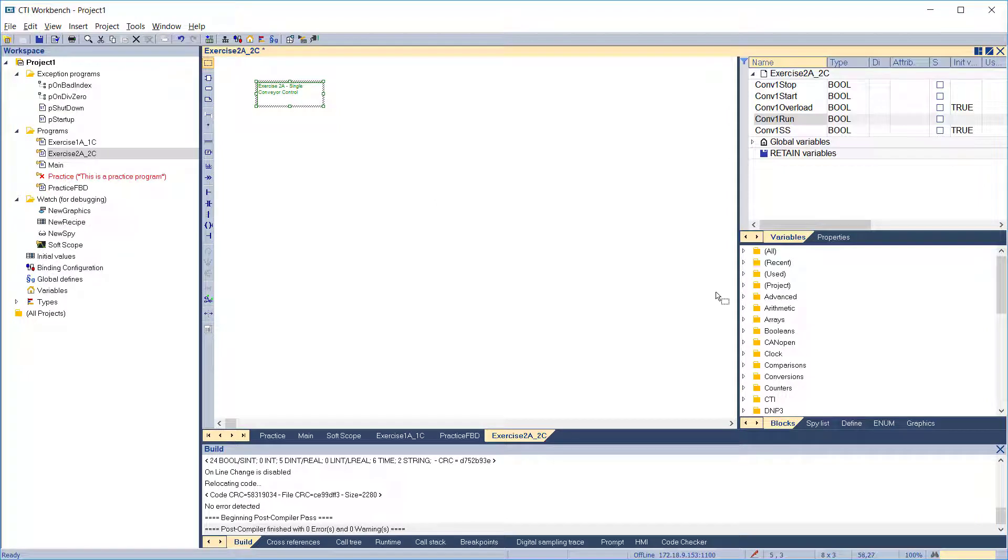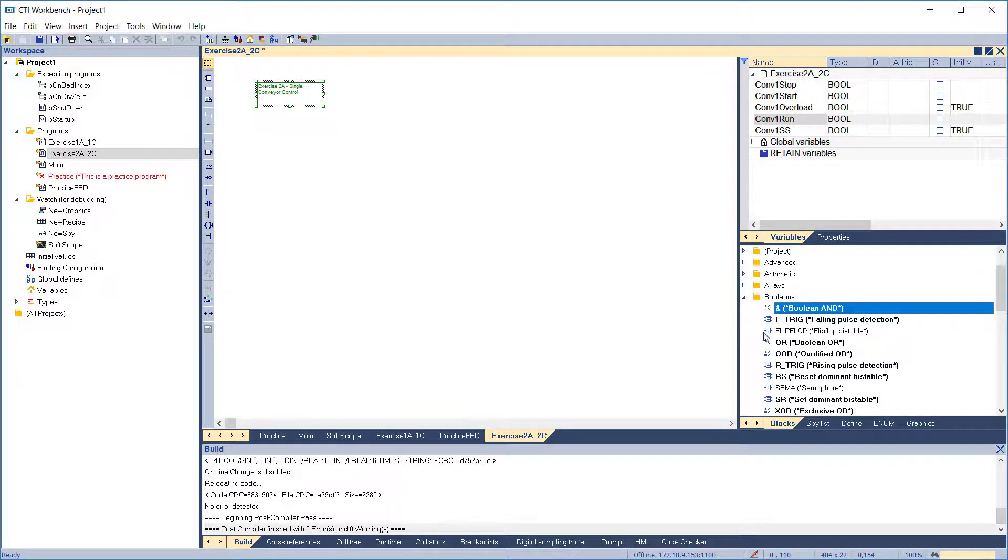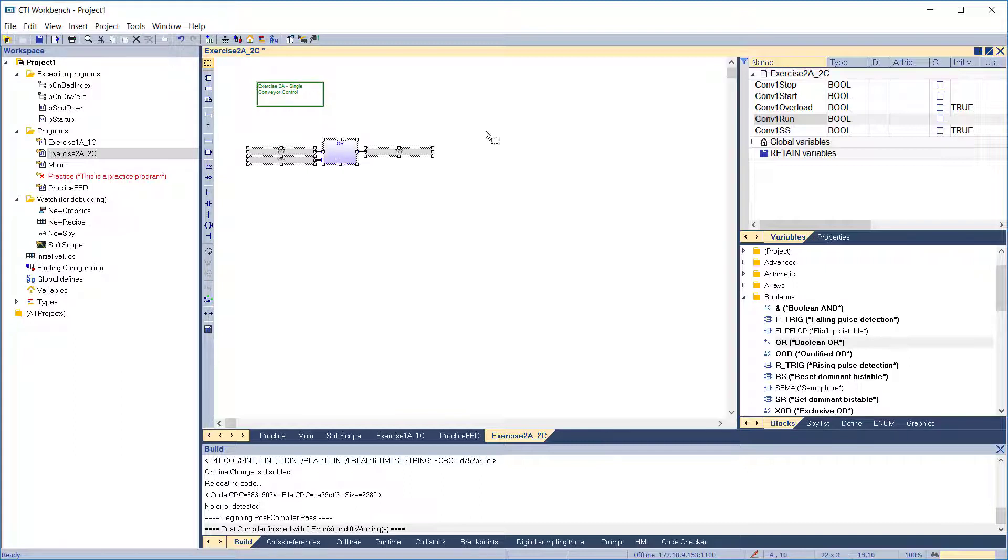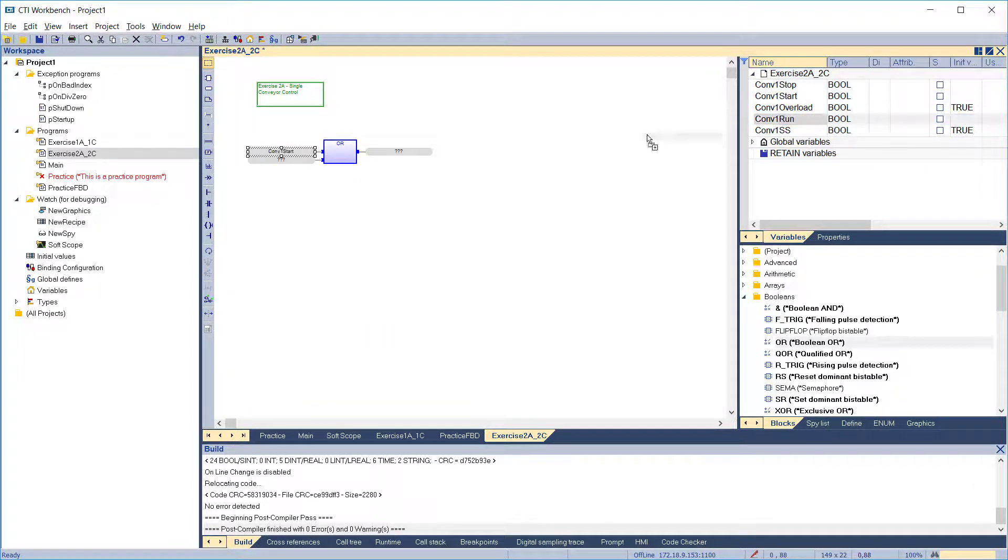This control can be accomplished with simple boolean functions, OR and AND. First, add the boolean OR function. Connect as inputs conveyor 1 start and conveyor 1 run to latch it in for running after the push button's released.